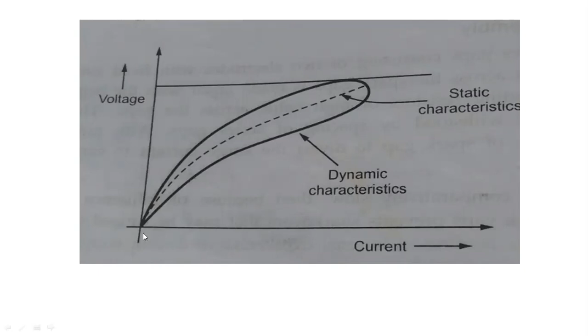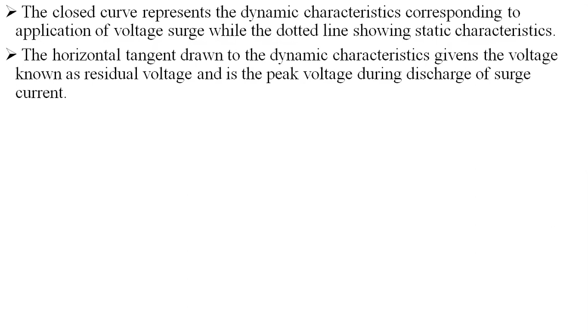The closed curve represents the dynamic characteristics corresponding to the application of voltage surge, while the dotted line shows the static characteristics. The horizontal tangent drawn to this dynamic characteristic gives the voltage known as residual voltage. See, this is the residual voltage. The tangent drawn to this dynamic characteristic is nothing but our residual voltage, and it is the peak voltage during the discharge of surge current.